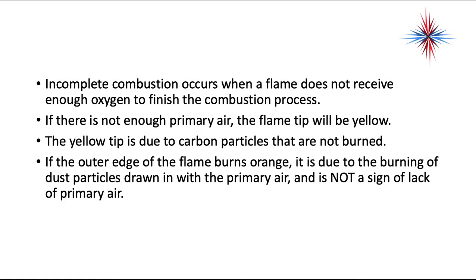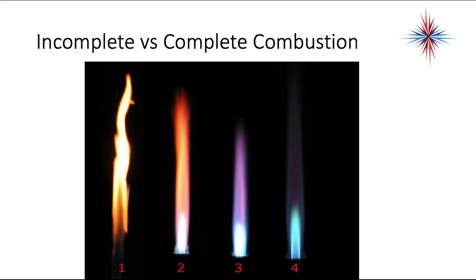Incomplete combustion occurs when a flame does not receive enough oxygen to finish the combustion process, and it's pretty dangerous. If there's not enough primary air, the flame tip will be yellow — due to carbon particles that are not burned. If the outer edge of the flame burns orange, it is due to dust particles drawn in with primary air; that is not a sign of lack of air. Yellow tips are the sign of lack of air. So we have incomplete combustion versus complete combustion: number one is a bad flame, number two is a bad flame, number three is okay, and number four is perfect combustion.